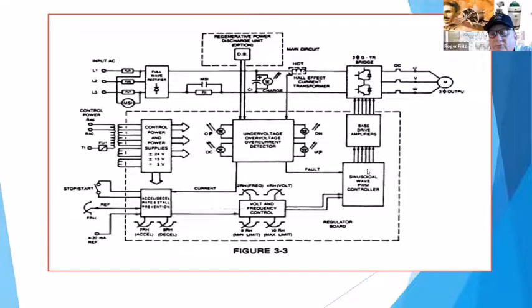So it was a control board that is basically just controlling when those pulses are coming out of the transistors provided to the motor. So again, you'll see the main circuit up here is pretty much identical. And we had undervoltage and overvoltage detection, which was basically just sensing, and we set where those trip points were so it could signal relays and those things. But everything was done. There just wasn't the digital processor to do all those things.